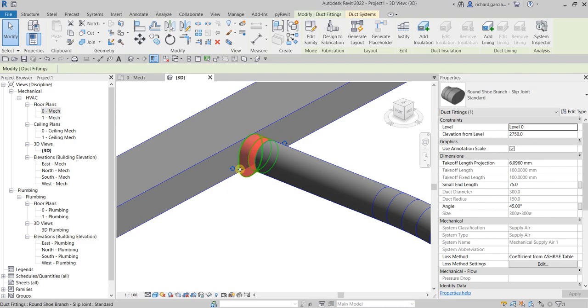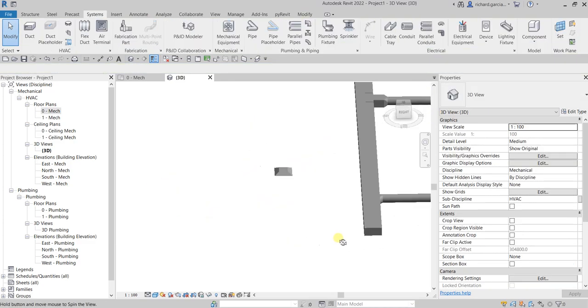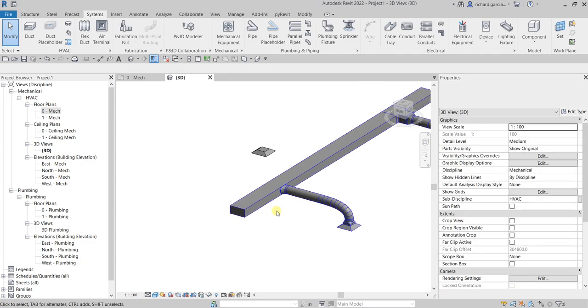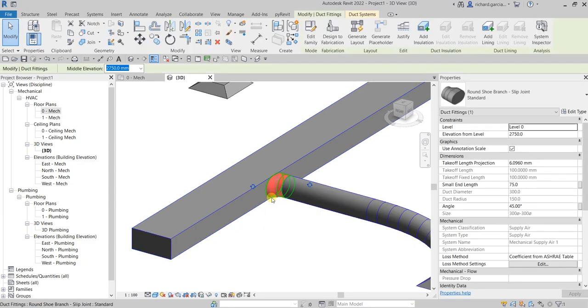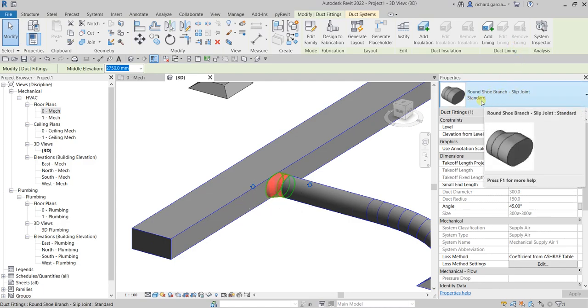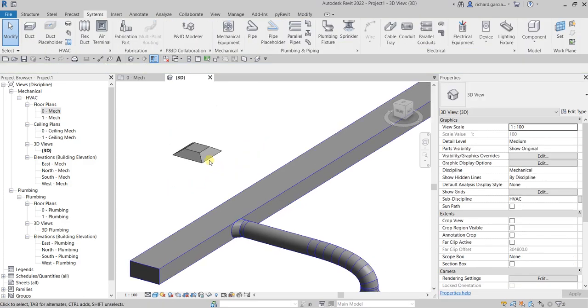If you check that in the 3D view, this is how it looks. You can rotate it to indicate the direction of airflow. Now let's say you want to change the type of that duct fitting — instead of a round shoe branch slip joint standard, you want to use a round fitting takeoff type. That is what we are going to do for the third air terminal.